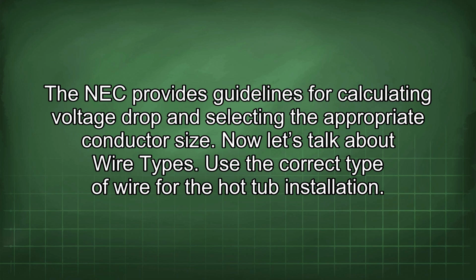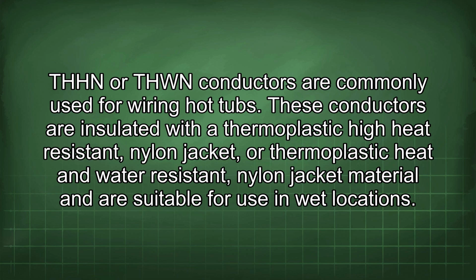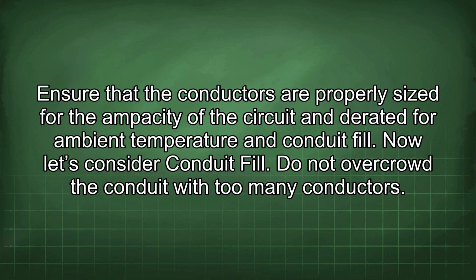Now let's talk about wire types. Use the correct type of wire for the hot tub installation. THHN or THWN conductors are commonly used for wiring hot tubs. These conductors are insulated with a thermoplastic high heat resistant nylon jacket or thermoplastic heat and water resistant nylon jacket material and are suitable for use in wet locations. Ensure that the conductors are properly sized for the ampacity of the circuit and derated for ambient temperature and conduit fill.